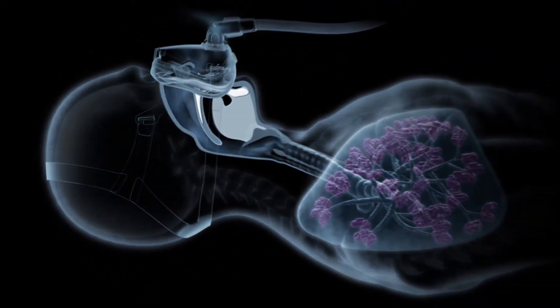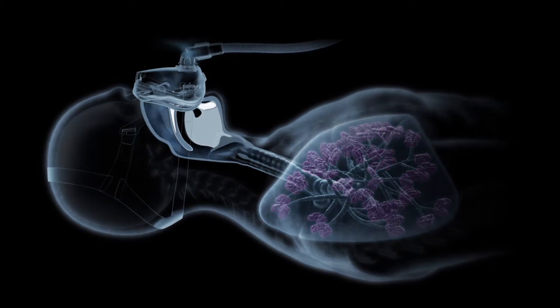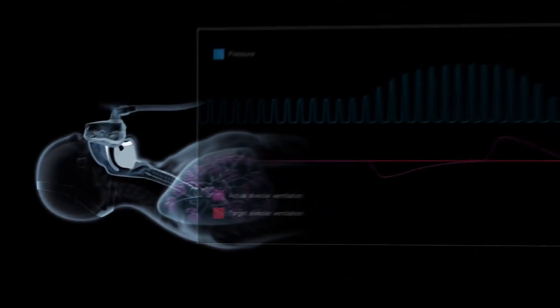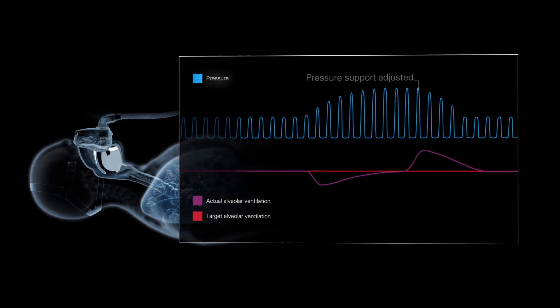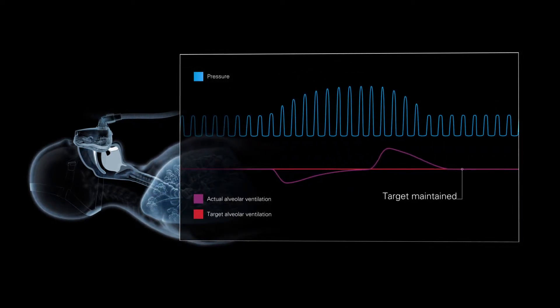It then continuously monitors the patient's actual alveolar ventilation and compares it to their target alveolar ventilation, automatically adjusting the level of pressure support to achieve and maintain their target alveolar ventilation.